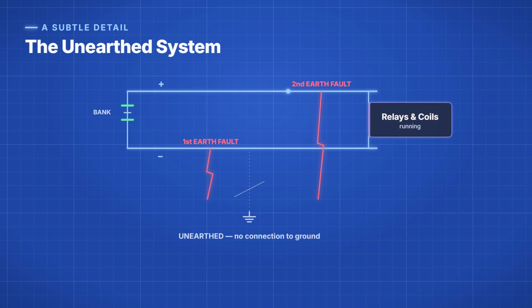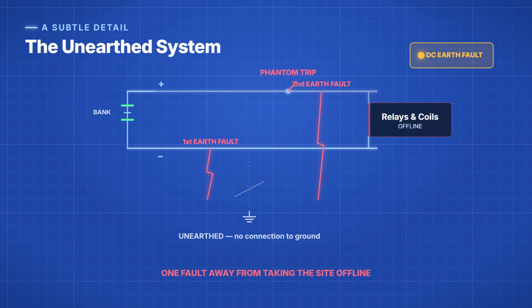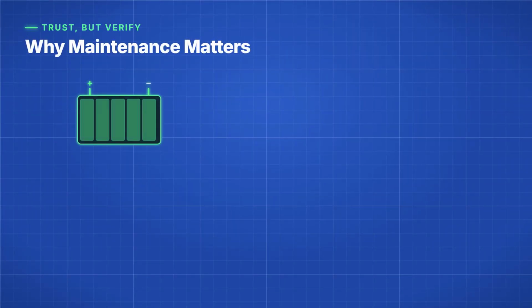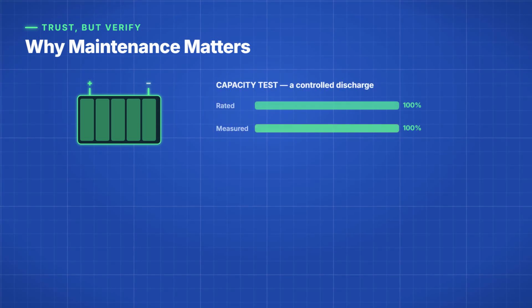So here is a practical field tip. The moment you see a DC earth fault alarm, nothing has tripped yet. The system is built to ride through it. But treat it as urgent because you are now just one fault away from a phantom trip that could take the entire site offline. All of this rests on one assumption, that the battery will actually deliver its rated capacity on the day it's needed.